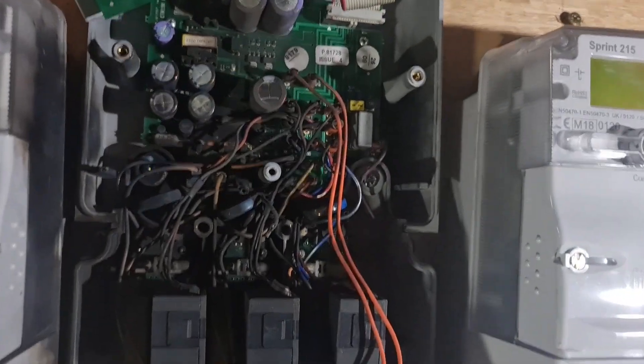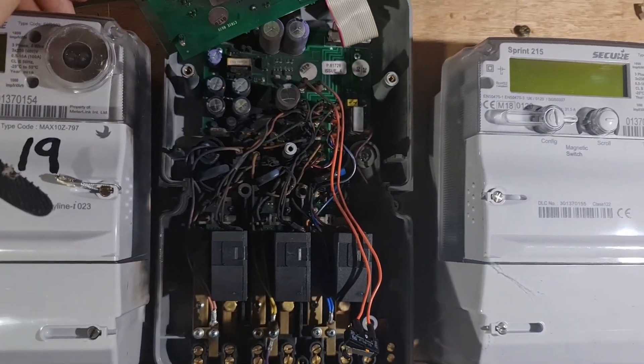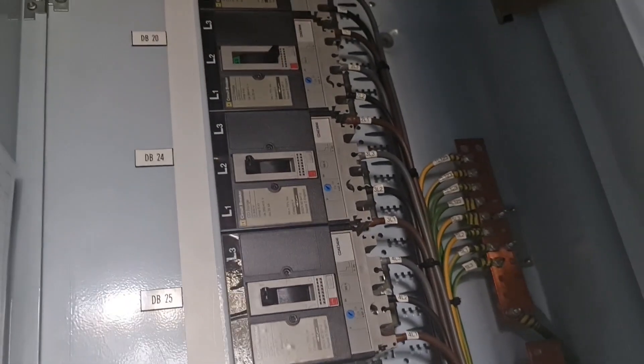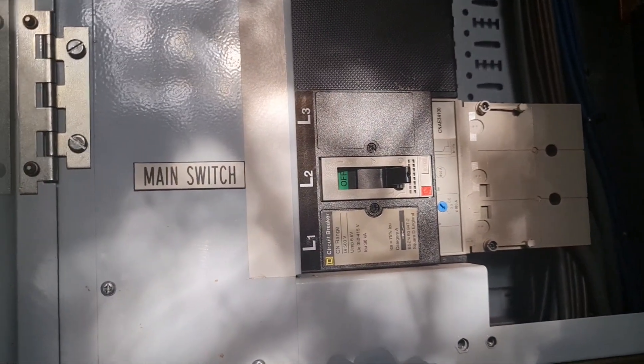I've just sent Matthew off — we brought the two of us over in case we had a bigger problem. He's going to look into unit 20 to make sure there's no problems inside there. I've got the meter apart — excuse the bad lighting, we're just running off torches — but it's got a bit crispy in there. It looks like we've lost a connection that's blown off, and it's actually internally shorted across all the phases. That's clearly why it's tripped off unit 20's MCCB, and that inrush of current has also taken out the main switch.